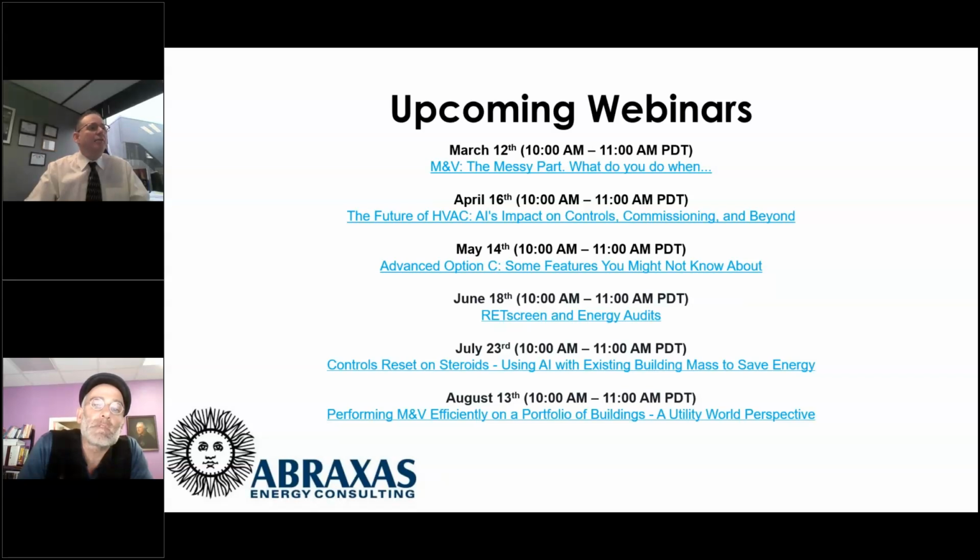I had a project with a private sector client, a comprehensive one. They were willing to spend the money primarily on controls so that when there was an alarm or an indicator that something went into hand, it actually told the facility manager after a certain set period, hey, this is still in hand. This is still overridden. Do you want to continue? And so what's my point? The owner was willing to pay for that level of programming within their control system.